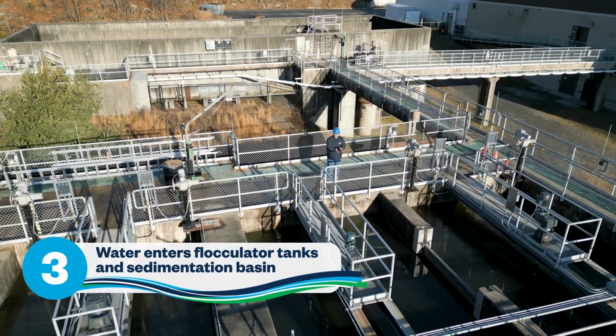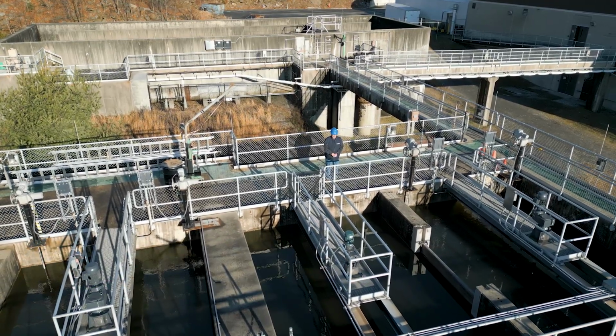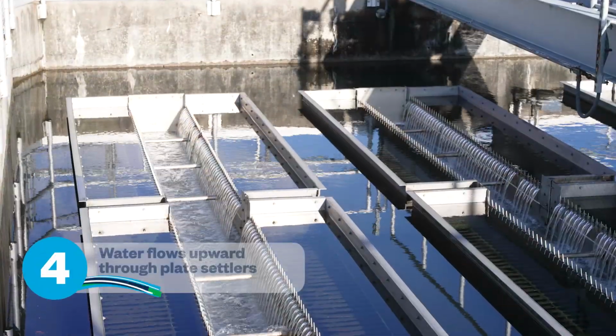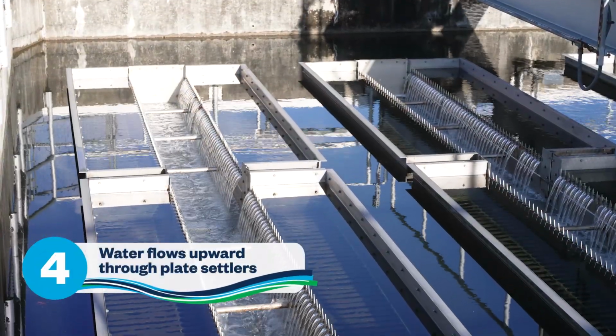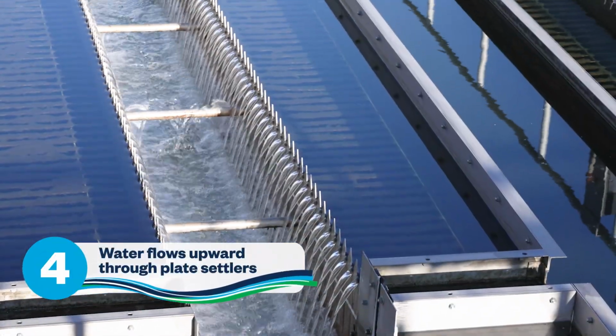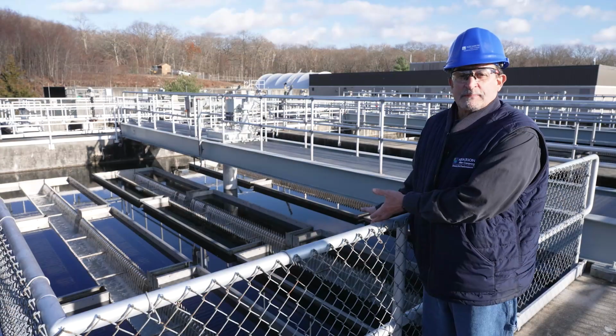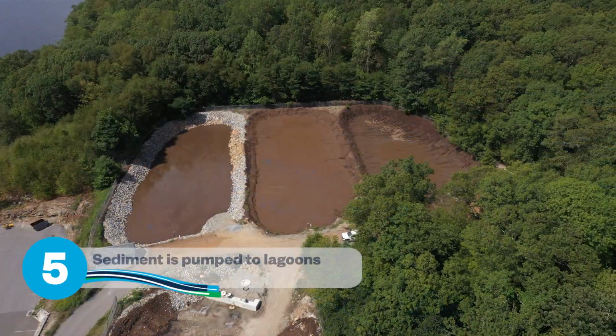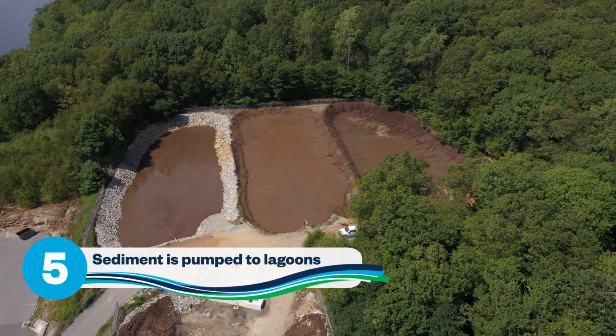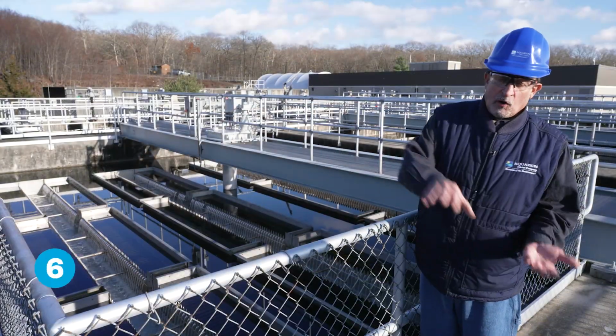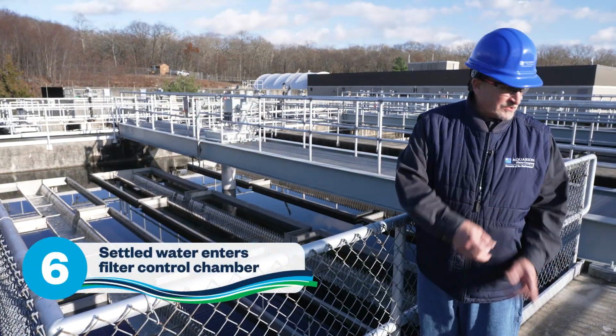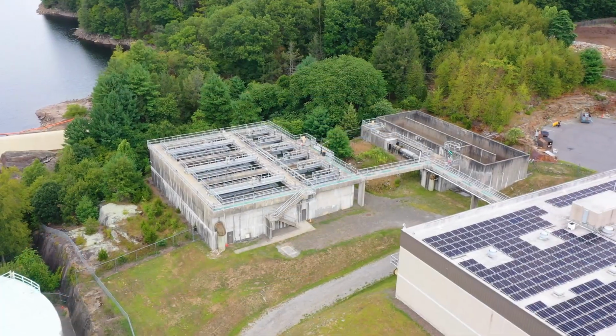That particle then flows across to the sedimentation basin for settling, then flows upward through these plate settlers. The particles settle out on the plate settlers, and then they settle to the bottom of this basin where they're collected and pumped to the lagoons. The settled water flows over into this channel, ultimately into the filters.